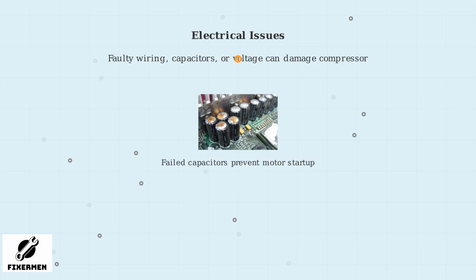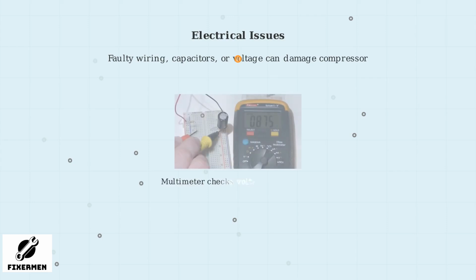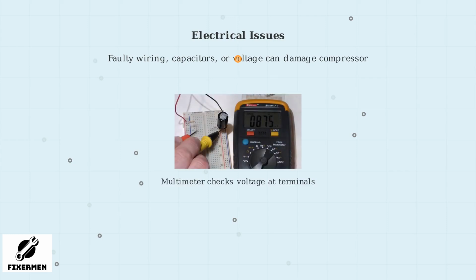Now let's look at electrical issues that can trigger the E4 error. Faulty wiring, capacitor problems, or voltage fluctuations can cause the compressor to overwork and overheat. Capacitors store electrical energy to start the compressor motor. Failed capacitors can prevent proper startup, causing the compressor to overheat as it struggles to run. Incorrect voltage supply can damage the compressor windings.